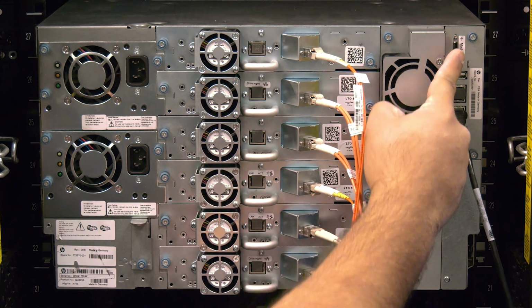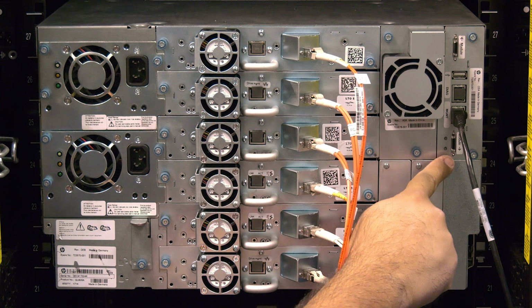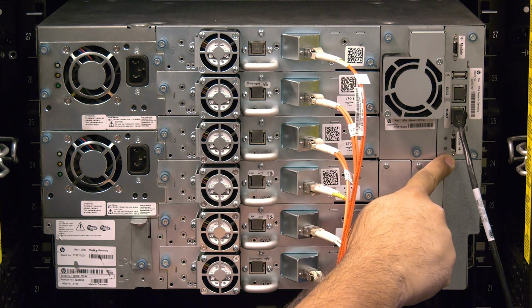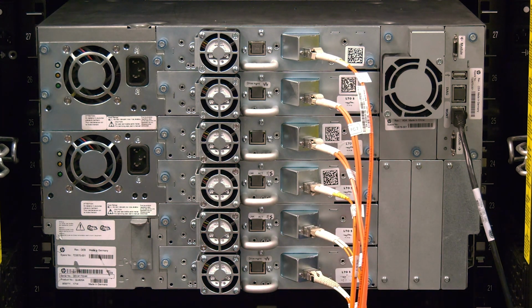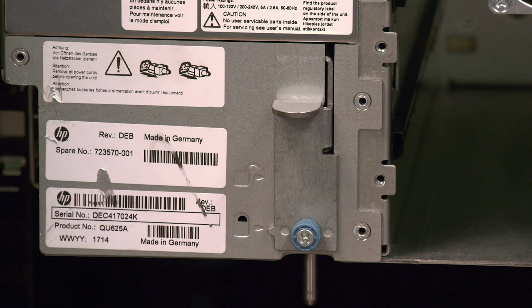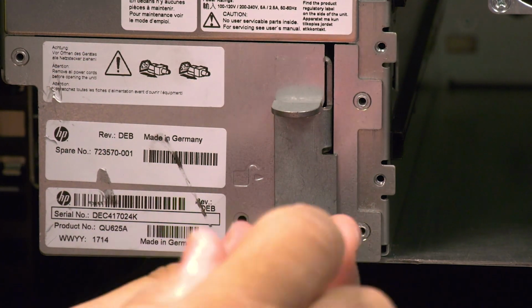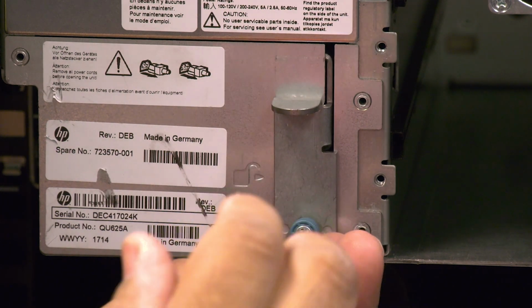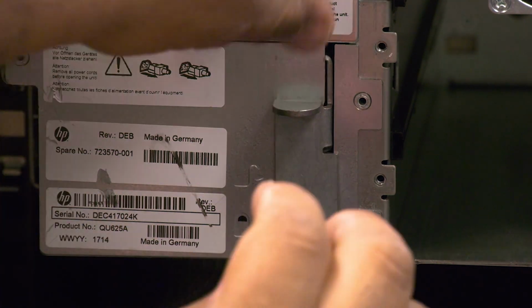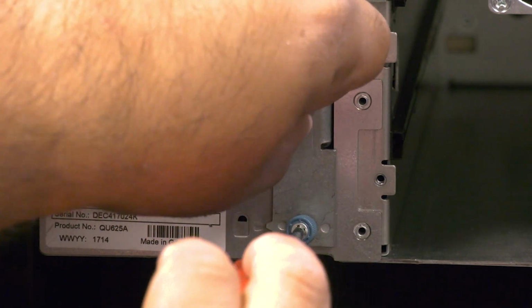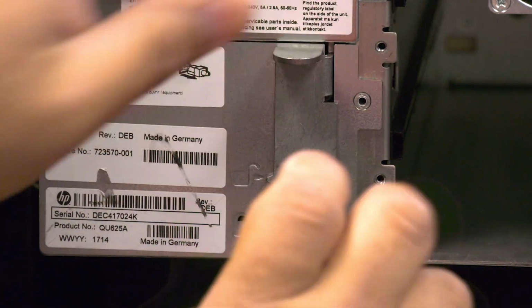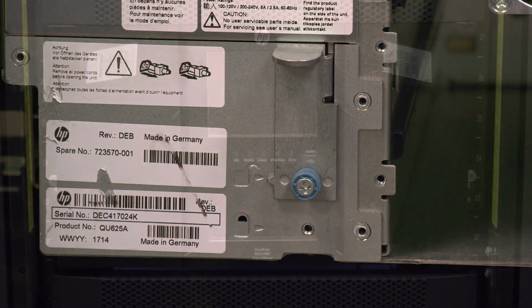Now, if you have any expansions above or below the control module, you will need to undo the interconnect cables that will be located at the top and bottom of the control module's control card, connecting them to the expansions. Then, you will also need to undo the thumb screws on the alignment mechanisms of both the control module and the expansion directly above it if it is present, and move the alignment mechanism from a locked to the unlocked position, and then retighten the thumb screws.